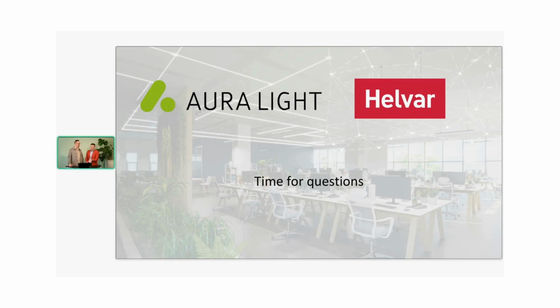A good question. So the Helvar ActiveAhead you have here is the wireless system from our side, and then we have the Helvar Imagine system, which is, let's say, traditionally wired, typically a DALI system. And yes, they can be combined in Insights, meaning that when you view that floor plan, you can see all the devices there, no matter whether they are wired or wireless. Of course, if it's, for example, your management looking at the occupancy or environmental data, they don't need to know what technology is behind it. When you call maintenance, for example, and you see there's a fault, then you need to know what the exact product or fault is, so you know who to call. But most of the data you see there is technology agnostic. So you can combine them as you wish.